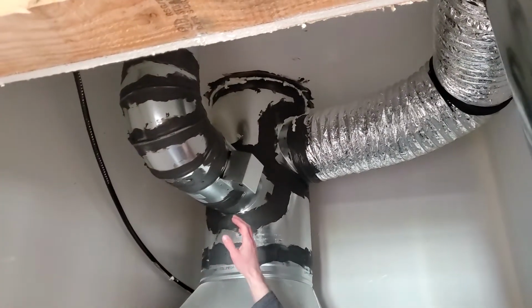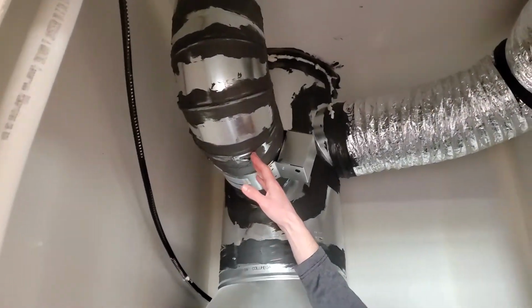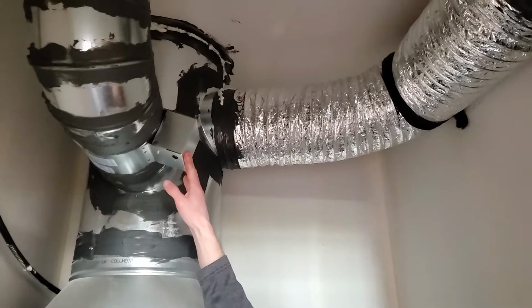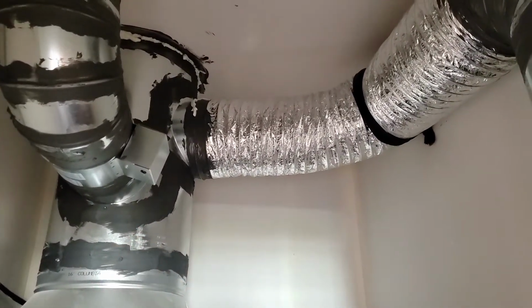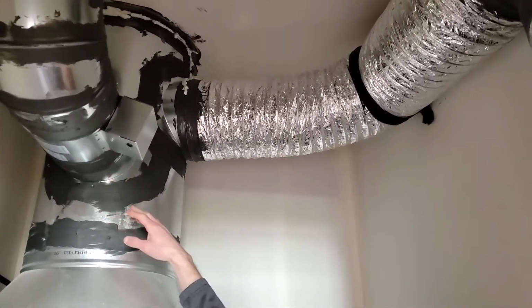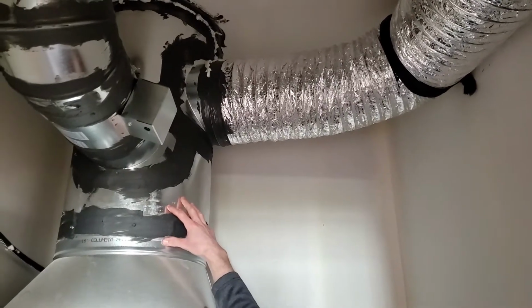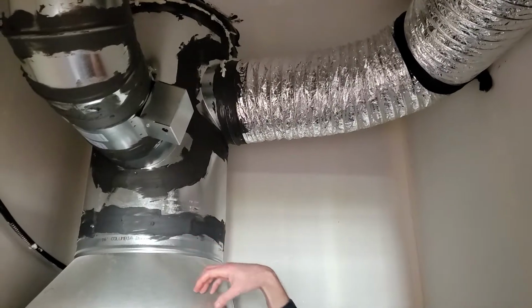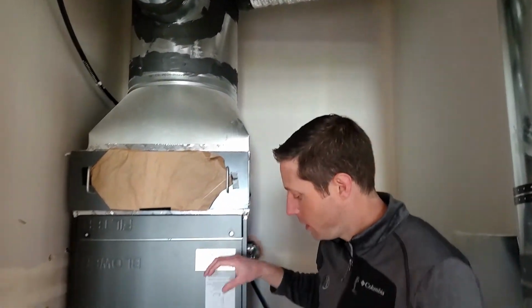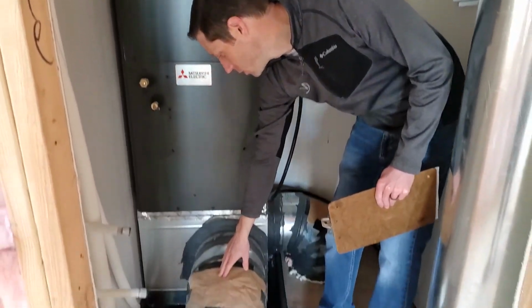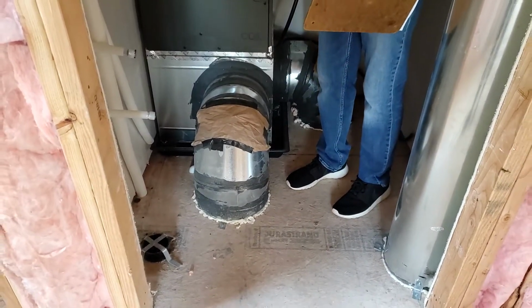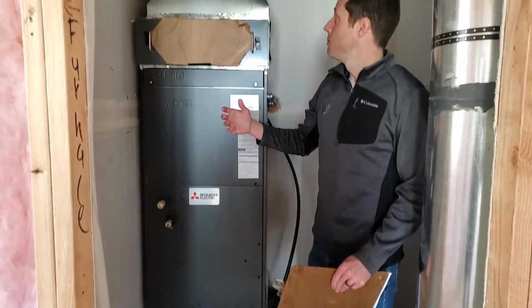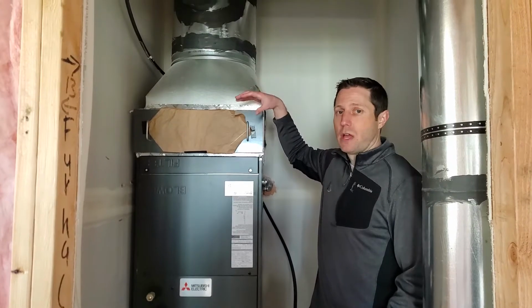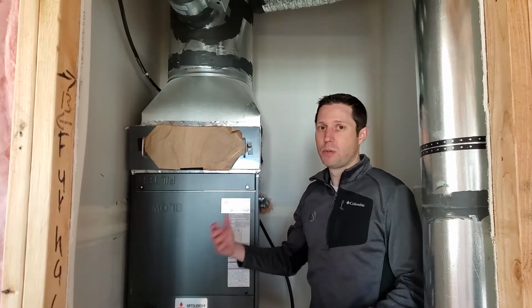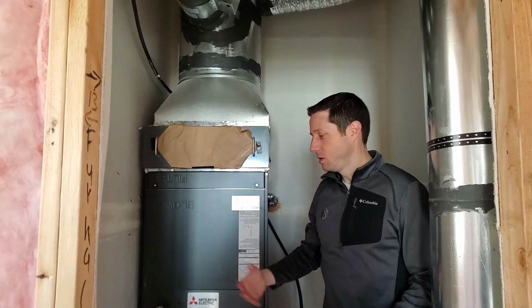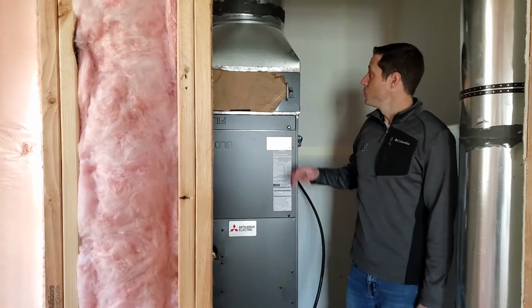So what we have here is a fresh air system. This is a duct that brings fresh air in from outside. This is a little damper that's electronically controlled, and this is going to get wired into a controller that's not present yet. But what happens is we bring this fresh air in, and we tie it into the return air system. That return air is then mixed with the outdoor air. It's sent through a filter here, and then it runs through the air handler, and it runs through our ductwork to the house. So we're distributing this fresh air all the way through the home after it's been filtered. And by mixing it in here, we're taking the indoor air temperature and the outdoor air temperature, and we're tempering that a little bit so we're not getting just a blast of the outdoor air. And it's filtered, so allergens are taken care of for that. It's a really good system.